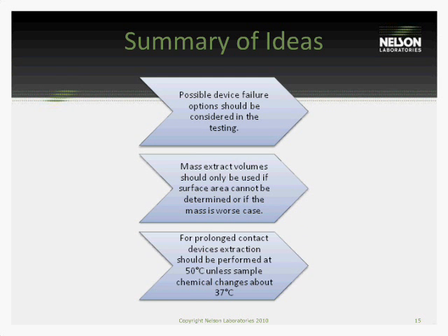There are different ways to do this, ways to maybe limit the amount of testing. We can look at the differences between inside and outside. We can look at the surface area compared to the whole device. So there are some good scientific ways to look at this, but you have to evaluate possible failure options of your device.